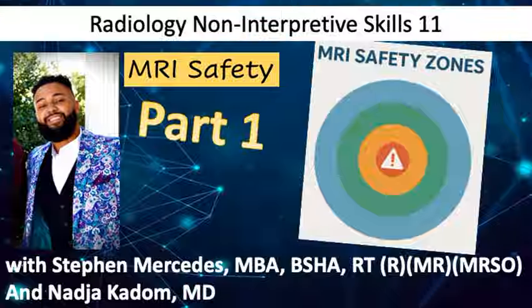Then you have the radio frequency energy. Radio frequency and gradient energies are turned on during the active scanning. Those concerns are more so regarding heating and also electromagnetic voltages going through, especially through the gradient field. So those are the three concerns. I always try to break those up by asking, are they going to be in the RF and gradient energy in the area being scanned? The static magnetic field is something that's always going to be on. So if it crosses that one and it's a concern for that, I don't even move forward with it, because it crosses off the list. So that's how I address it.